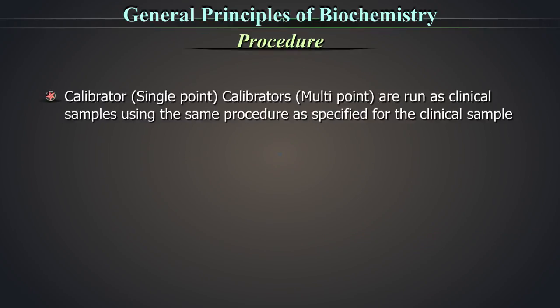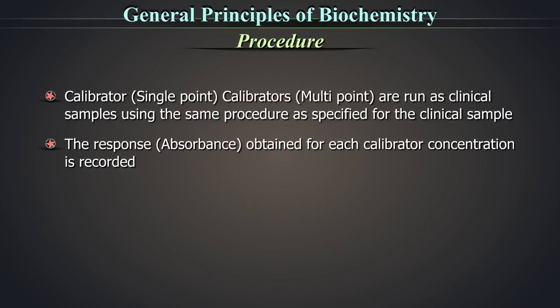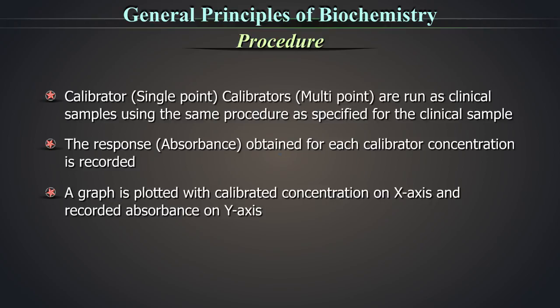Procedure: Calibrator single point or calibrators multipoint are run as samples using the same procedure as specified for the clinical sample. The response, i.e. absorbance, is obtained for each calibrator concentration. It is recorded. A graph is plotted with calibrator concentration on the x-axis and the recorded absorbance on the y-axis.